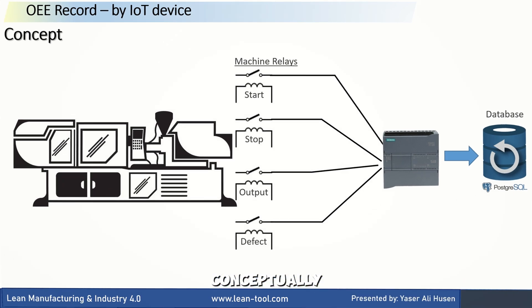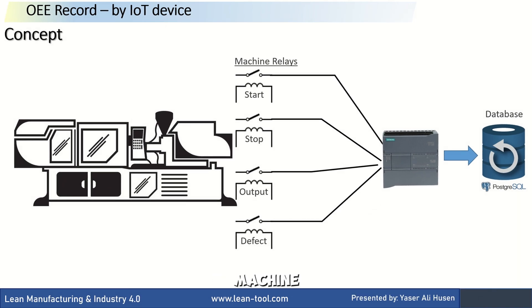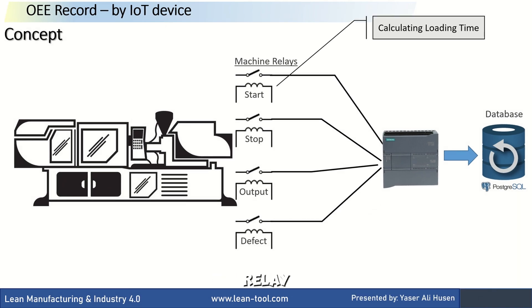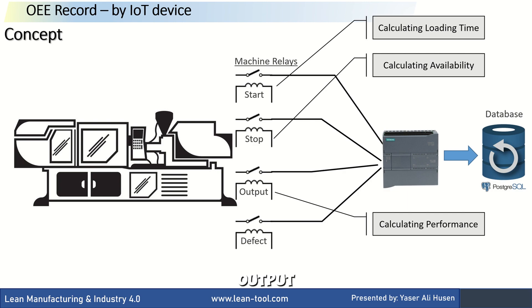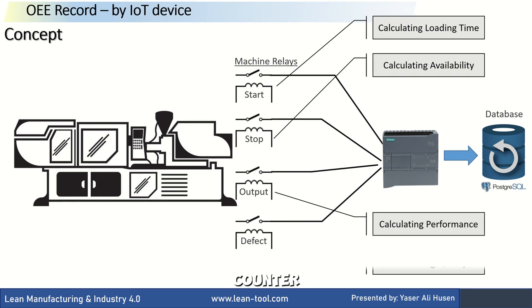Conceptually, we'll use four relays for each machine. These include a start relay to calculate loading time, a stop or downtime relay to calculate availability, an output relay as an output counter to calculate performance, and an additional relay, the defect counter, to calculate quality.